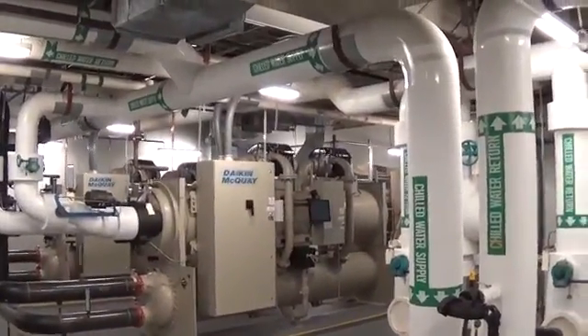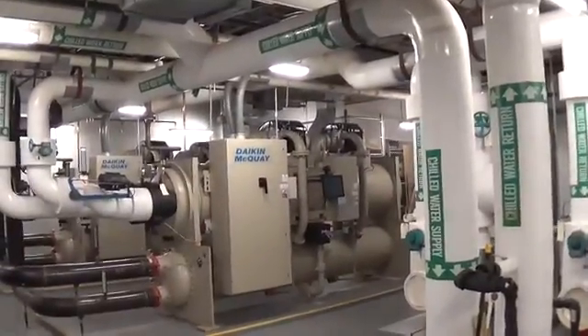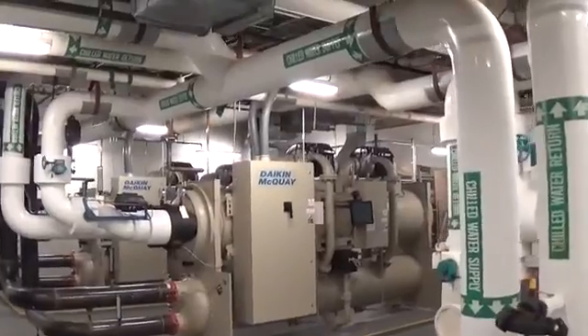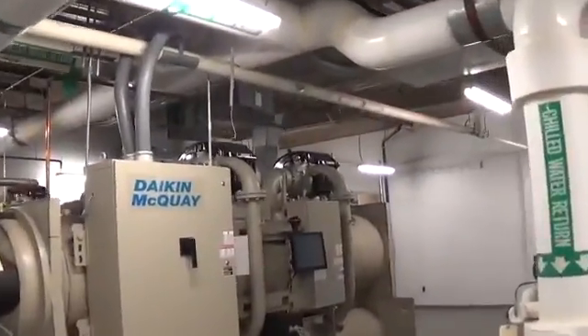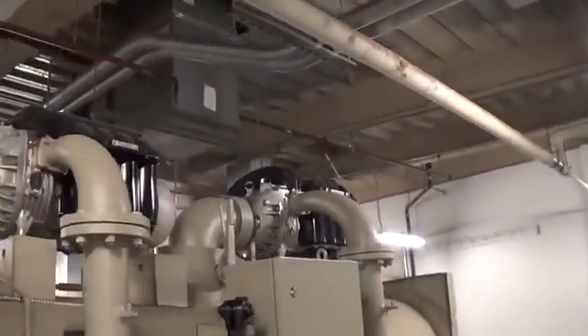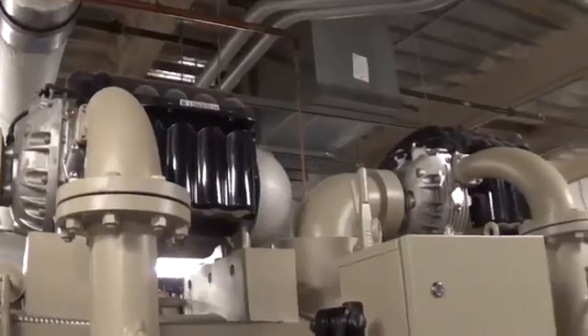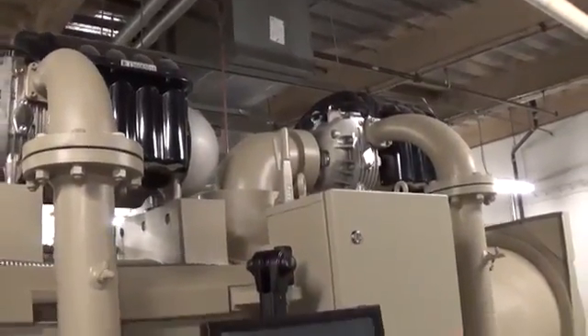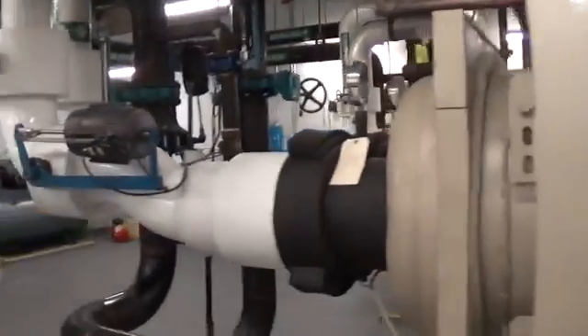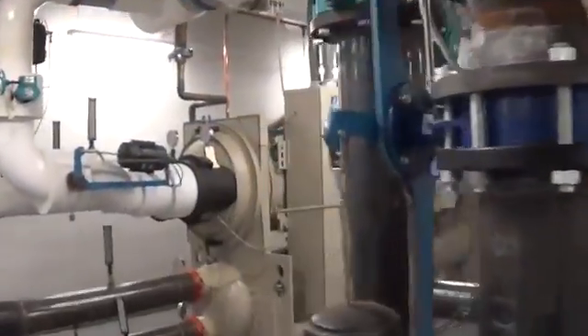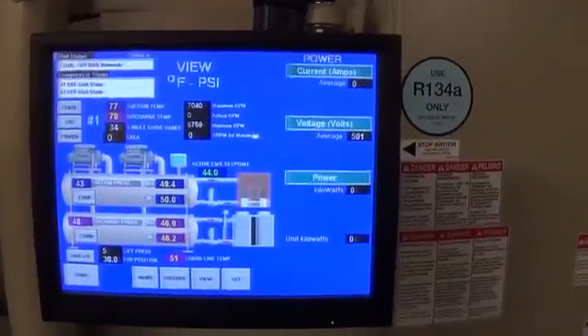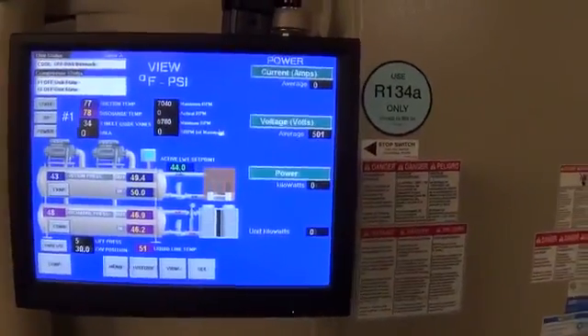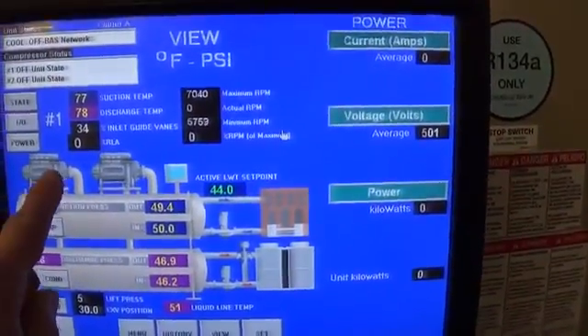If you look closely on the top of the chiller there, and I will do my best to zoom in here a little bit, you will see that these have high-tech motors on the top that actually use no oil. These motors run in a suspended animation, so they have no real friction, and they save you a ton of money on electrical over the old-fashioned chillers. Both of these chillers are not running. It's a very cold morning here. I'm going to walk over to this one, and you can see it has a really nice screen on there that gives you some eye candy of pretty much what's happening with the machine as far as pressures go and temperatures. Here you can see the little motor nomenclature on top.